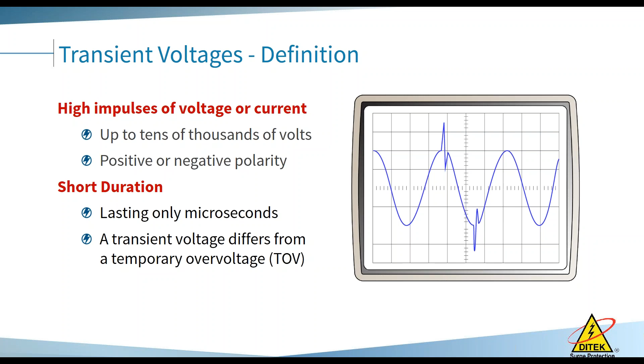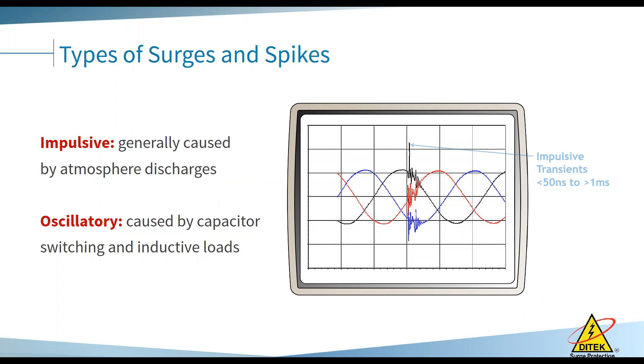Types of surges and spikes: impulsive and oscillatory. Impulsive are your atmospheric ones, like when people hear a lightning bolt or thunder. That's what we consider impulsive, atmospheric discharge. Oscillatory surges seem to be the larger cause of surges in most properties. These come from capacitor switching and inductive loads, such as pumps, motors, drives, HVAC, chillers, and elevator motors. Whenever they turn on and turn off, they tend to generate surges inside a property.